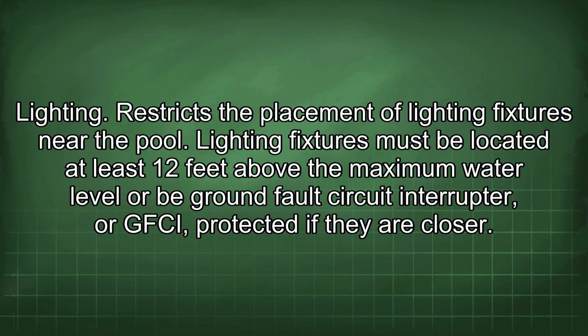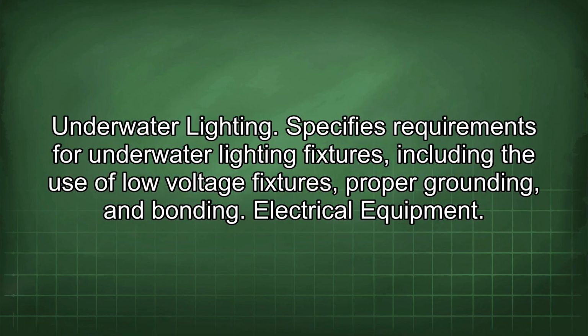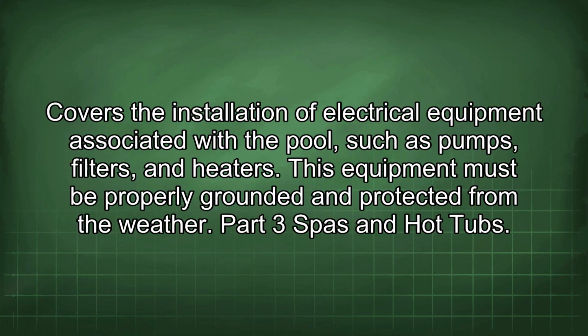Lighting. Restricts the placement of lighting fixtures near the pool. Lighting fixtures must be located at least 12 feet above the maximum water level or be ground fault circuit interrupter, or GFCI, protected if they are closer. Underwater lighting. Specifies requirements for underwater lighting fixtures, including the use of low voltage fixtures, proper grounding, and bonding. Electrical equipment. Covers the installation of electrical equipment associated with the pool, such as pumps, filters, and heaters. This equipment must be properly grounded and protected from the weather.